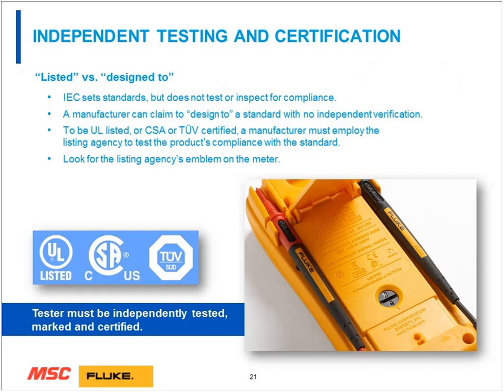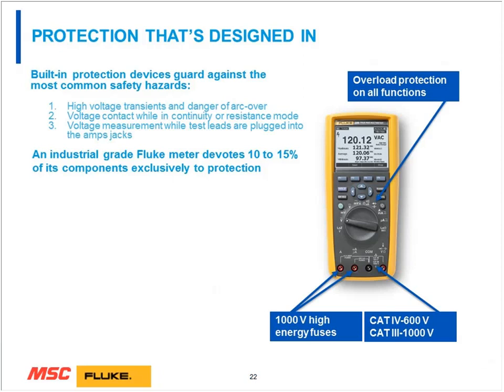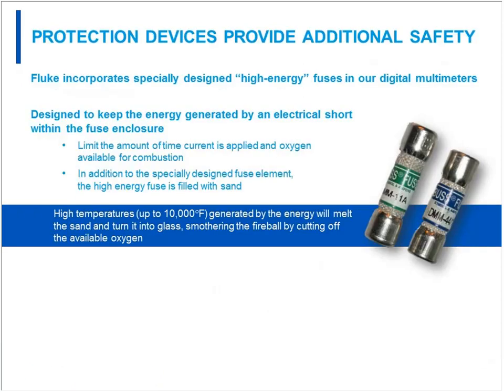There's also independent testing and certification that goes through each piece of instrument. So take the instrument out of its protective holster, flip it over, take a look for CSA, TUV, UL listings, and that guarantees that in fact they still work well. Excuse me. Protections designed in. So with instruments, they use high voltage, high energy fuses that are actually sand filled to extinguish an arc. We have other overload protection and other capabilities that keep the instrument safe. About 10 to 15% of the cost of going into the meter is devoted to these safety features.